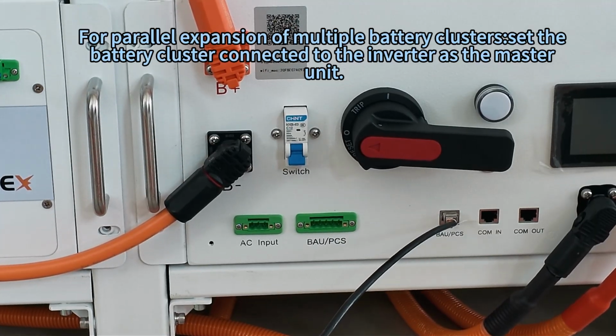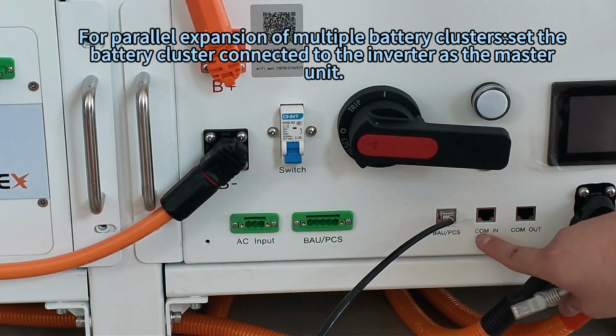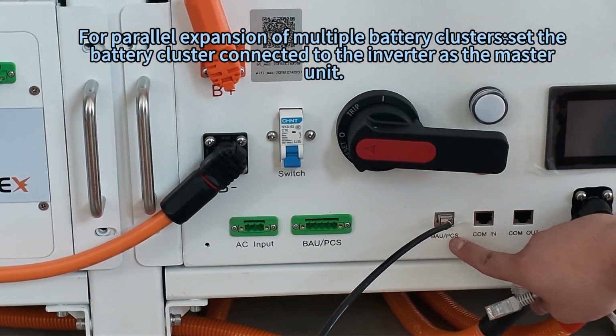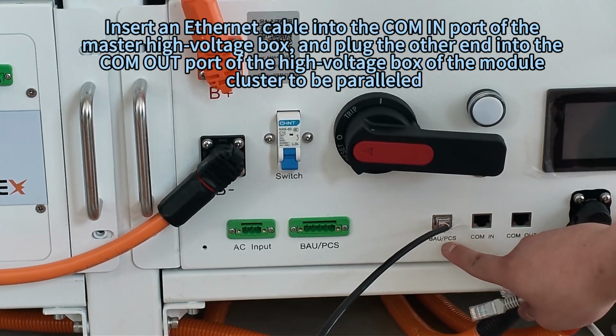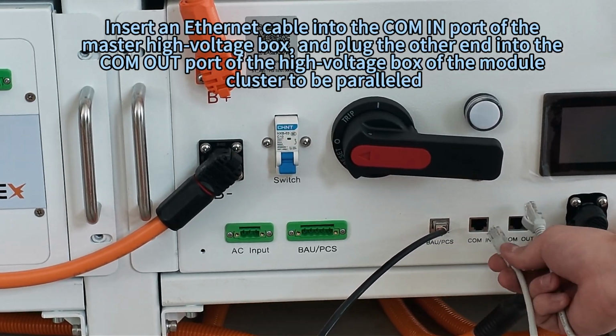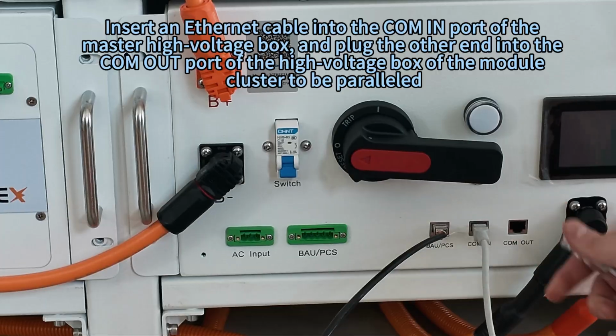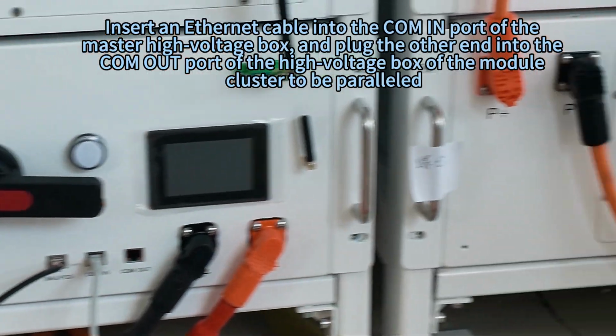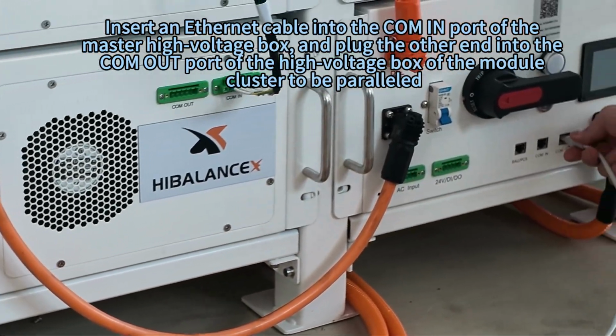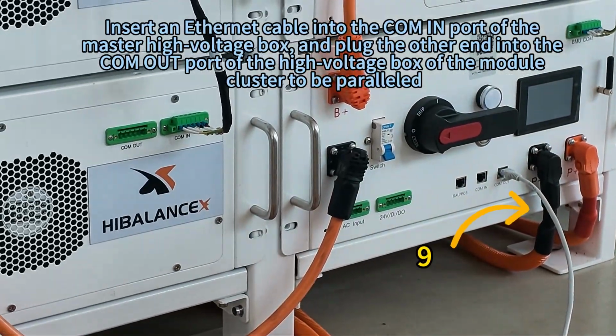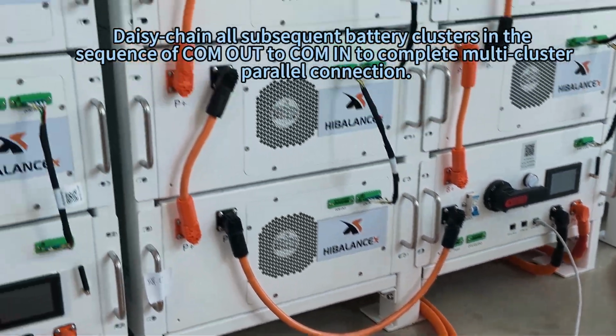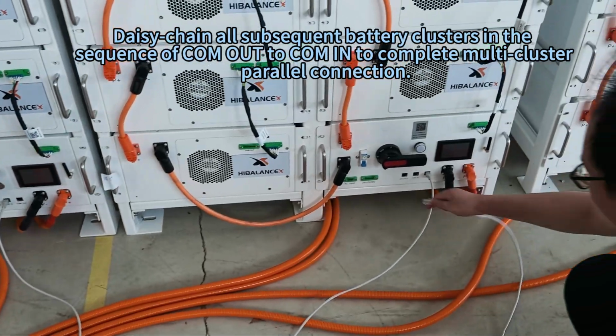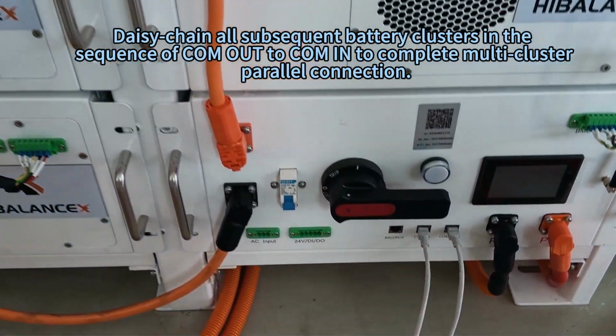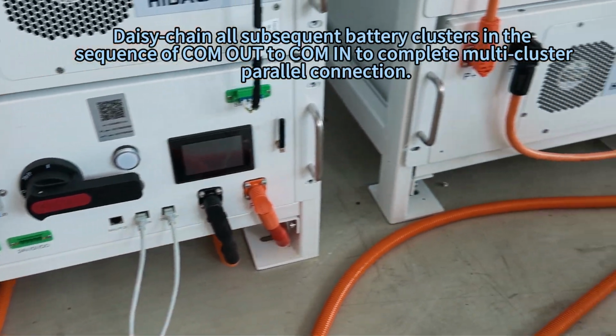For parallel expansion of multiple battery clusters, set the battery cluster connected to the inverter as the master unit. Insert an Ethernet cable into the COM IN port of the master high voltage box and plug the other end into the COM OUT port of the high voltage box of the module cluster to be paralleled. Daisy chain all subsequent battery clusters in the sequence of COM OUT to COM IN to complete multi-cluster parallel connection.